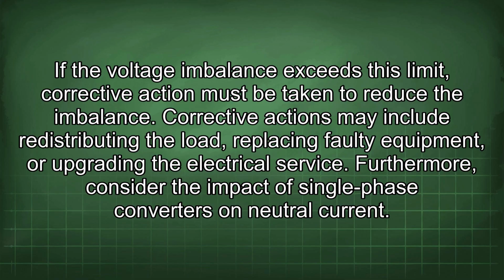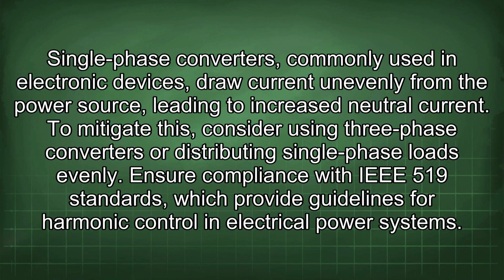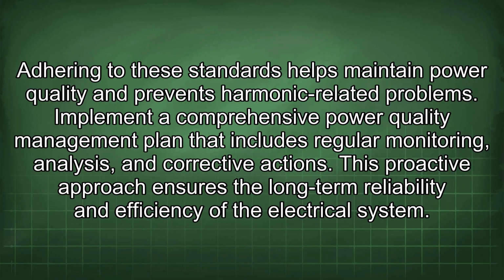Furthermore, consider the impact of single-phase converters on neutral current. Single-phase converters, commonly used in electronic devices, draw current unevenly from the power source, leading to increased neutral current. To mitigate this, consider using three-phase converters or distributing single-phase loads evenly. Ensure compliance with IEEE 519 standards, which provide guidelines for harmonic control in electrical power systems. Adhering to these standards helps maintain power quality and prevents harmonic-related problems. Implement a comprehensive power quality management plan that includes regular monitoring, analysis, and corrective actions. This proactive approach ensures the long-term reliability and efficiency of the electrical system.